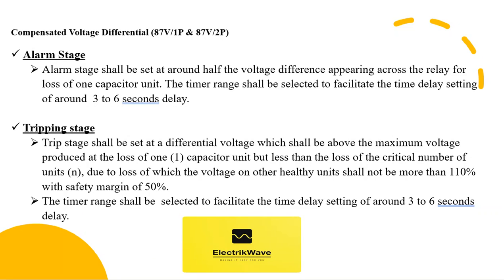Alarm stage shall be set at around half the voltage difference appearing across the relay for loss of one capacitor unit. The timer range shall be selected to facilitate the time delay setting of around 3 to 6 seconds. Trip stage shall be set at a differential voltage which shall be above the maximum voltage produced at the loss of one capacitor unit, but less than the loss of the critical number of units due to loss of which the voltage on other healthy units shall not be more than 110%, with a safety margin of 50%. The timer range shall be selected to facilitate the time delay setting of around 3 to 6 seconds.